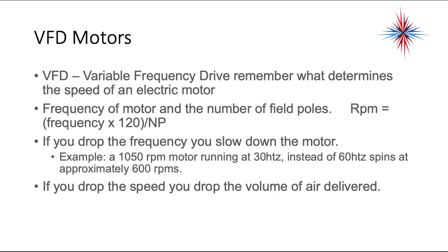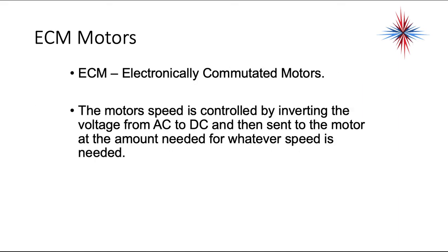A VFD is a variable frequency drive. Remember what determines the speed of an electric motor: it's the frequency and the number of poles. The formula is: RPM = frequency × 120 divided by the number of poles. If you drop the frequency, you can slow down the motor. For example, a 1050 RPM motor running at 30 hertz instead of 60 hertz spins at approximately 600 RPM. If you drop the speed, you drop the volume of air delivered.